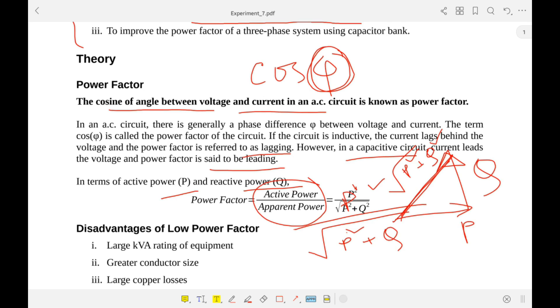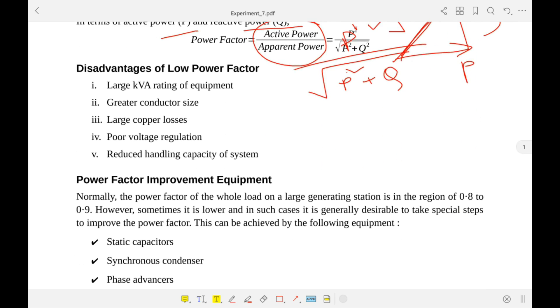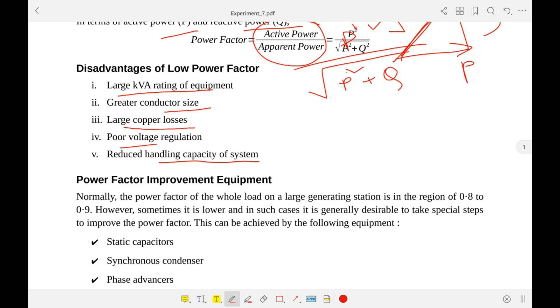The disadvantages of lower power factor — why do we need power factor improvement? If the power factor is low, we need large kVA rating of equipment, meaning motors and generators must be larger in size. We also need greater conductor size to transmit the same amount of power. There are large copper losses, poor voltage regulation, and reduced system capacity.